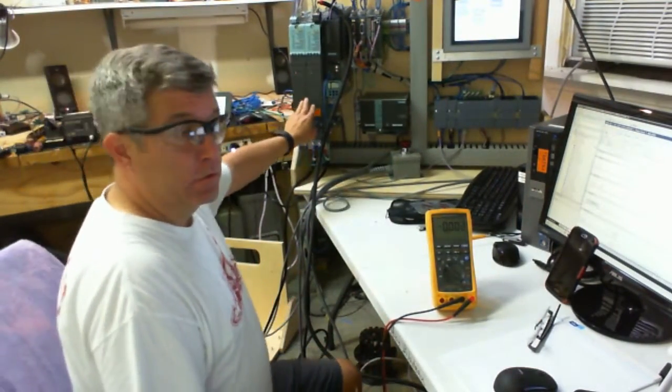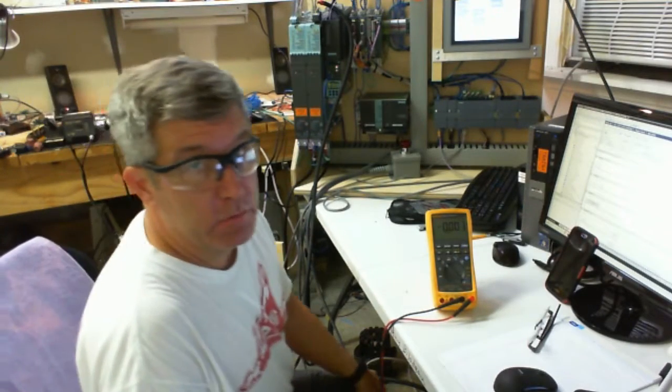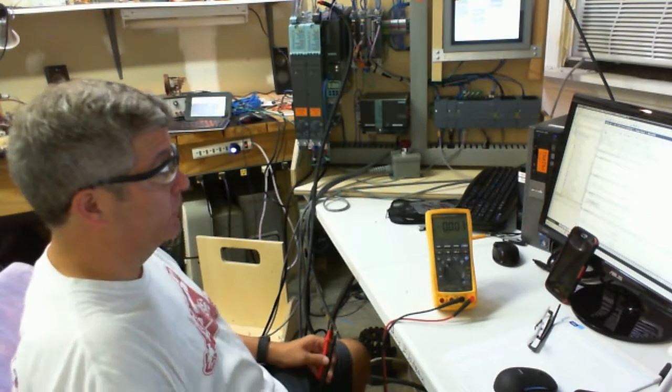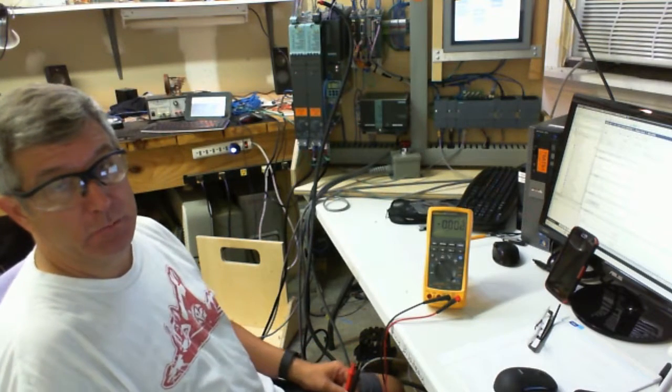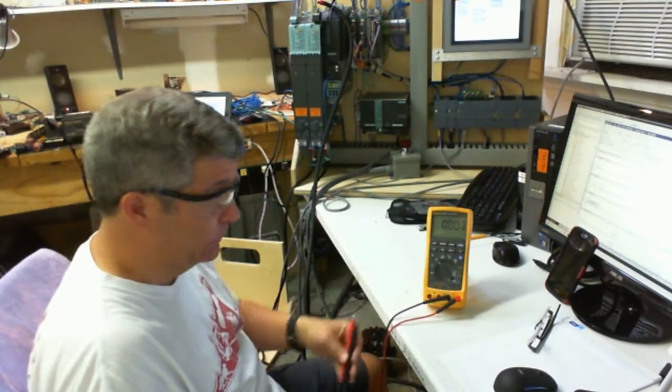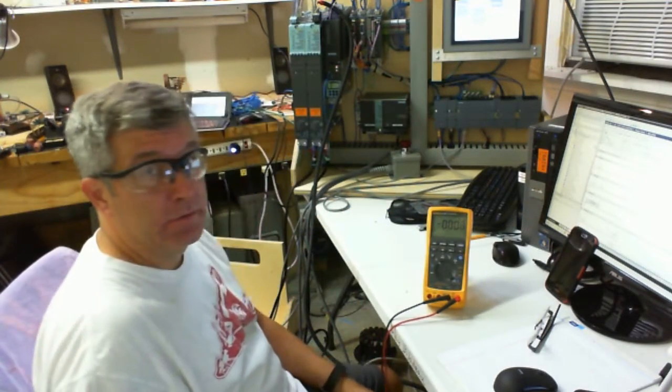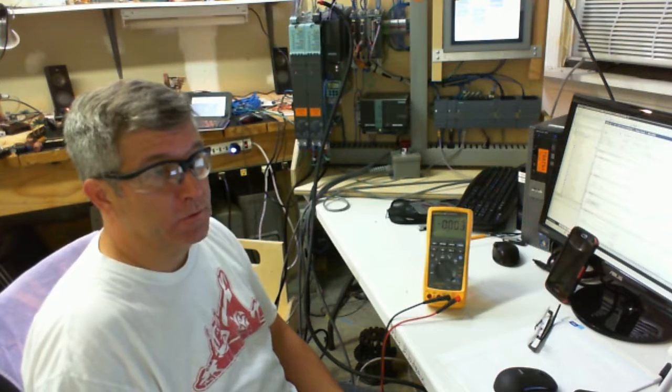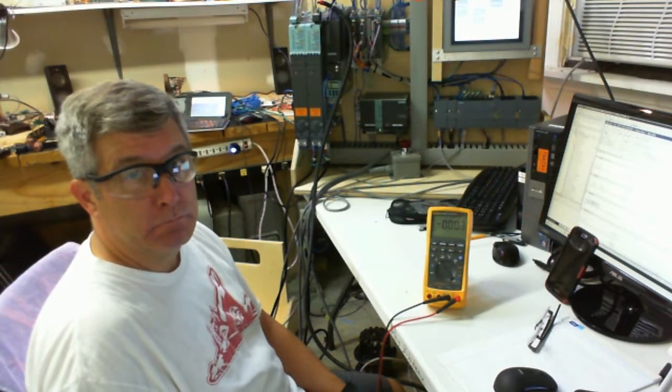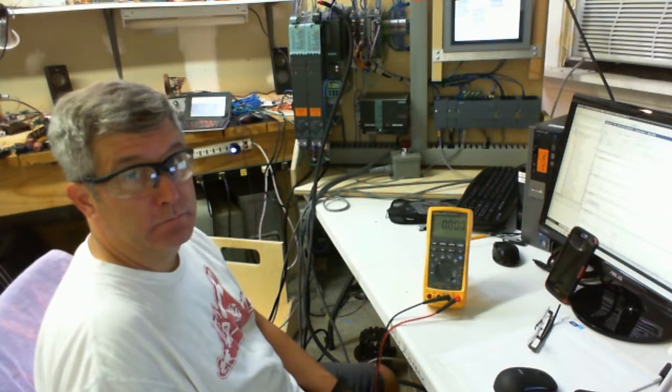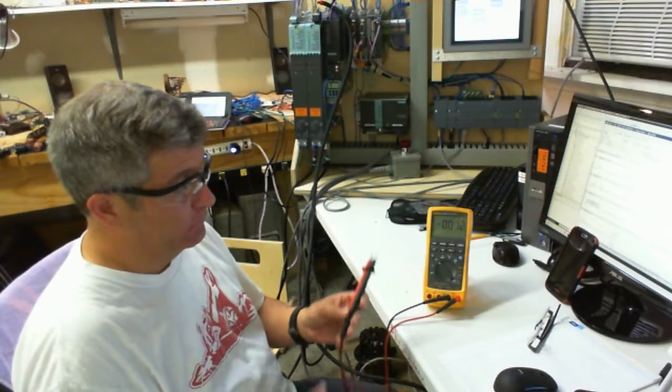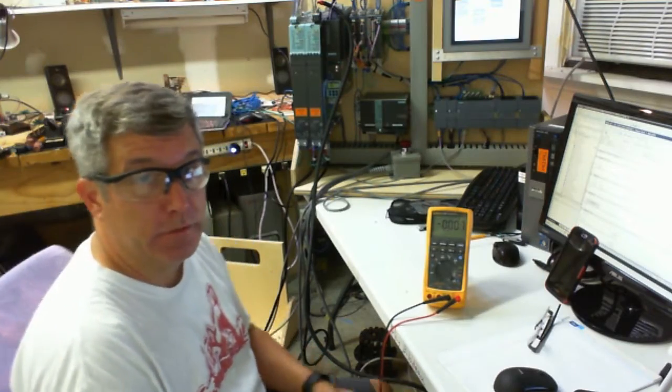A lot of drives will have a little LED that says the drive is powered up internally. It's a half cent LED. Don't trust your life to it. You've got to have a multimeter. Make sure you have a multimeter that's rated for 1,000 volts with leads that are rated for 1,000 volts. That isn't the one you're going to find at Walmart. You can go to any of the good websites out there selling equipment. Get yourself a meter that has a 1,000 volt rating. Spend more than 30 bucks, and that way you know you're going to be safe.